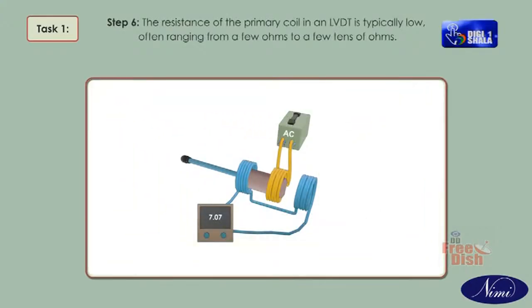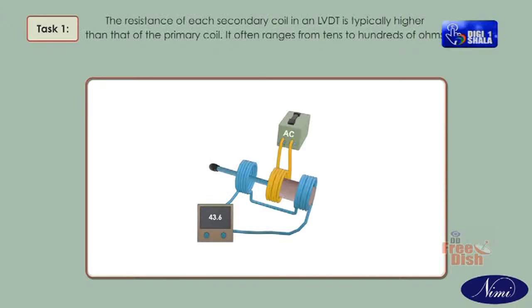Step 6. The resistance of the primary coil in an LVDT is typically low, often ranging from a few ohms to a few tens of ohms. The resistance of each secondary coil in an LVDT is typically higher than that of the primary coil. It often ranges from tens to hundreds of ohms.